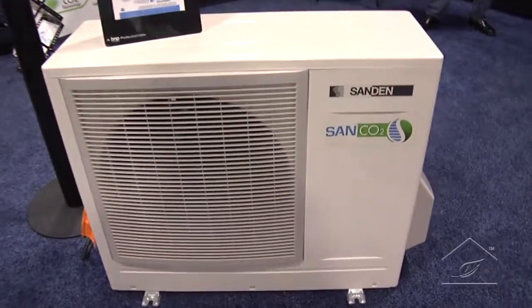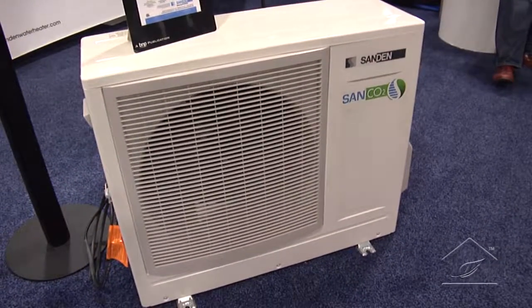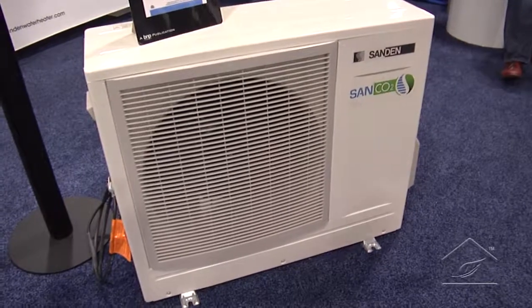As the tank fills up with cold water because you're showering, doing dishes, or whatever, that cold water stays at the bottom but the hot always stays at the top. When the system kicks on, it puts more hot water in at the top and pushes down that plug of cold water — a dynamic that's quite different from a normal water heater. And the unit really likes that cold water coming back, because it's all about the lift: lifting that water from 45°F to 150°F is where we get the big bang for the buck.